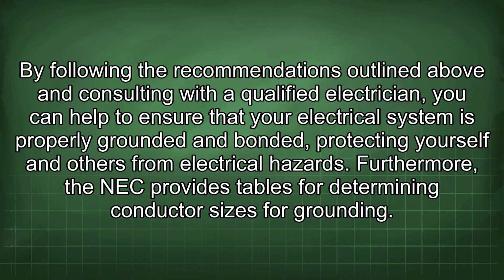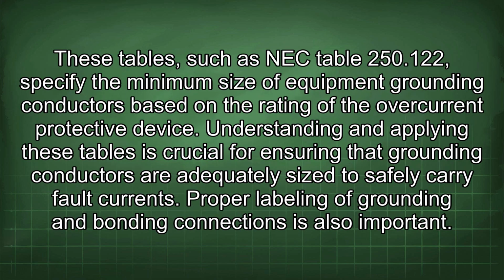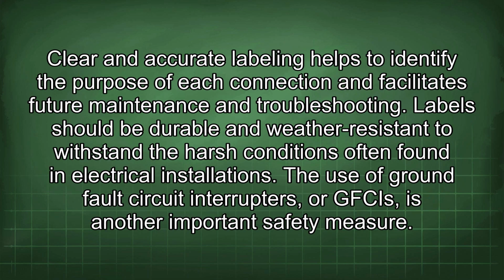Furthermore, the NEC provides tables for determining conductor sizes for grounding. These tables, such as NEC Table 250.122, specify the minimum size of equipment grounding conductors based on the rating of the overcurrent protective device. Understanding and applying these tables is crucial for ensuring that grounding conductors are adequately sized to safely carry fault currents. Proper labeling of grounding and bonding connections is also important. Clear and accurate labeling helps to identify the purpose of each connection and facilitates future maintenance and troubleshooting. Labels should be durable and weather-resistant to withstand the harsh conditions often found in electrical installations.